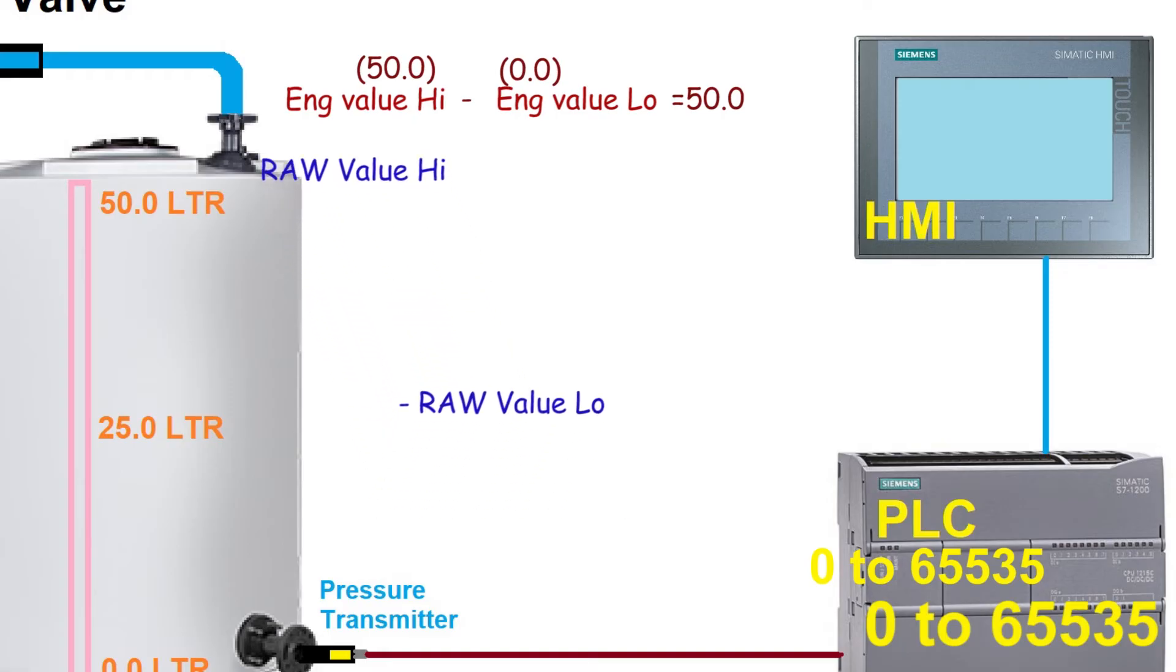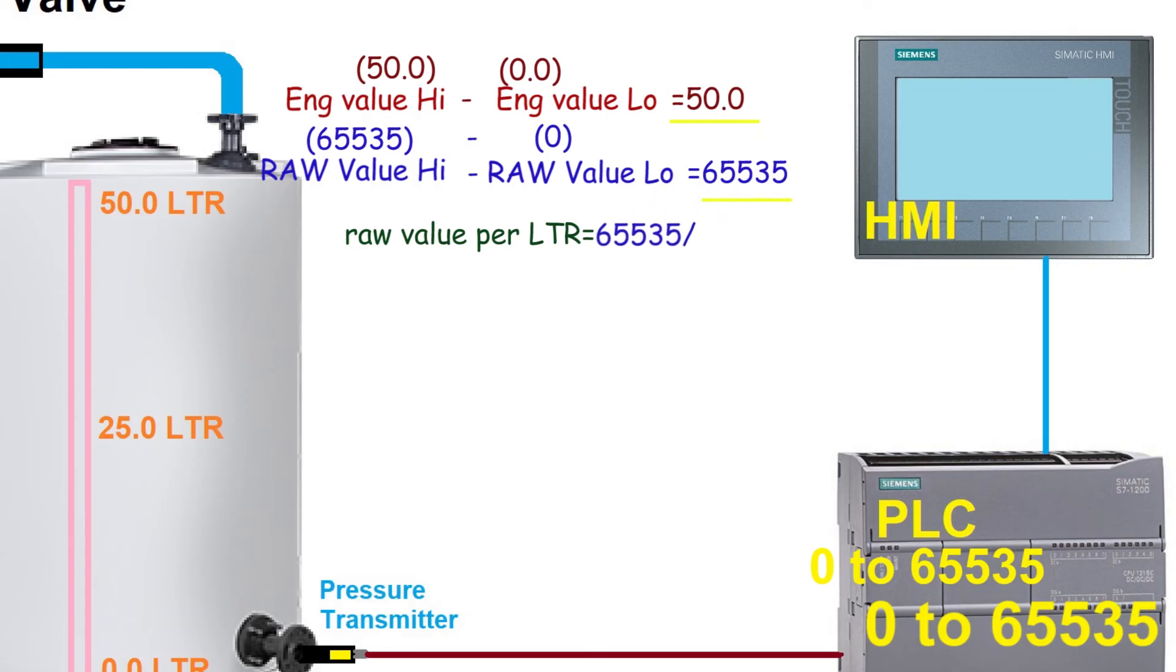Then we will minus raw high value with raw low value which is 65535 minus 0 equals 65535. From these two values we can calculate raw value count per liter which is 65535 divided by 50 and it is equal to 1310.7.